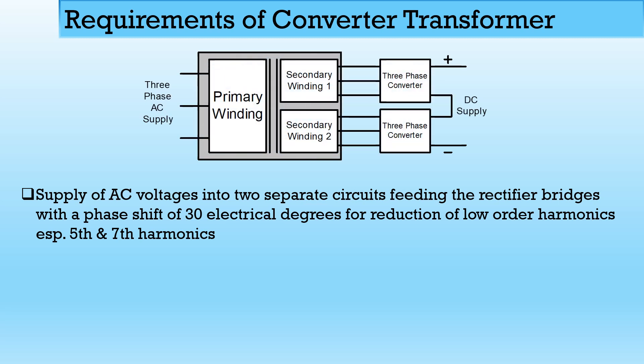There is one primary winding and two secondary windings. The EMF induced in the first part has 0-degree phase shift with the primary, whereas the EMF induced in the second part has 30-degree phase shift. The output of both three-phase converters are connected together — each is a 6-pulse converter, and together they form a 12-pulse converter — giving DC output voltage.